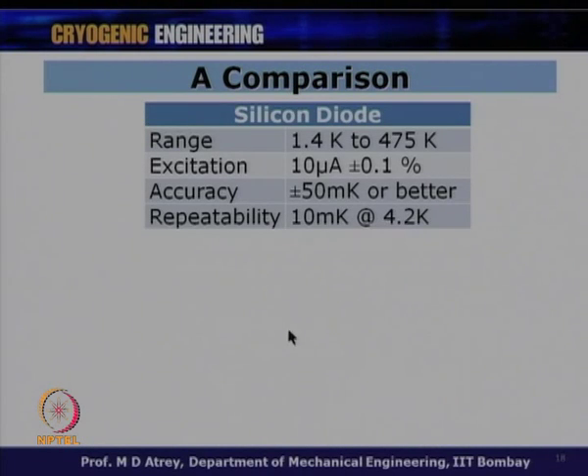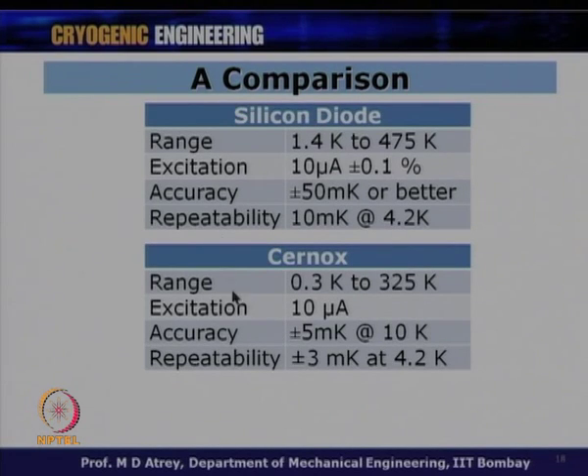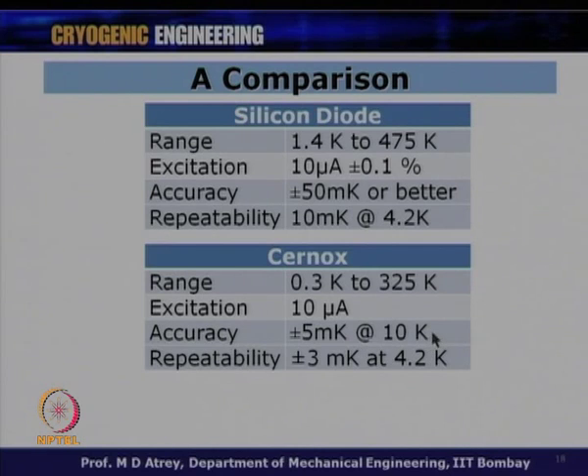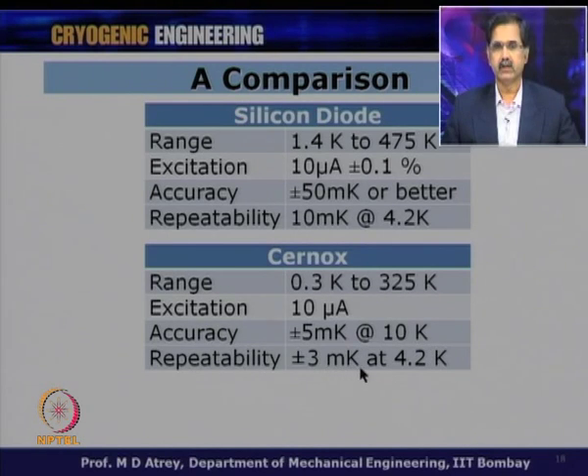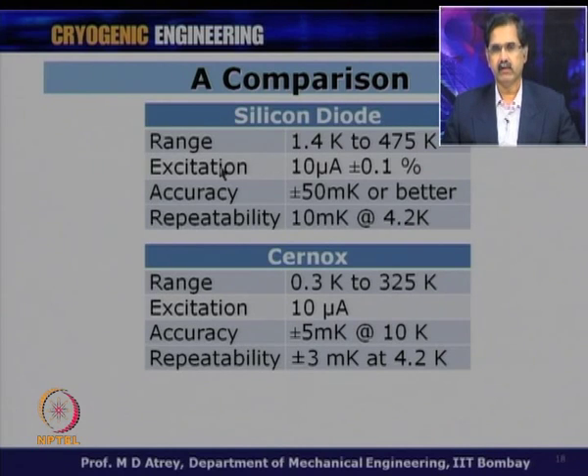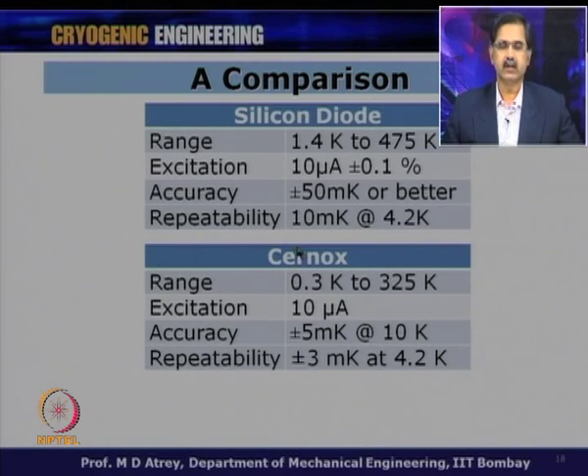Comparing silicon diode and Cernox: silicon diode operates from 1.4 K to 475 K; Cernox from 0.3 K to 325 K. Both use 10 microamp excitation. Silicon diode accuracy is ±50 milli-Kelvin; Cernox is ±5 milli-Kelvin at 10 K. Repeatability is ±3 milli-Kelvin for Cernox and ±10 milli-Kelvin at 4.2 K for silicon diode. These are comparative representative values from various references.